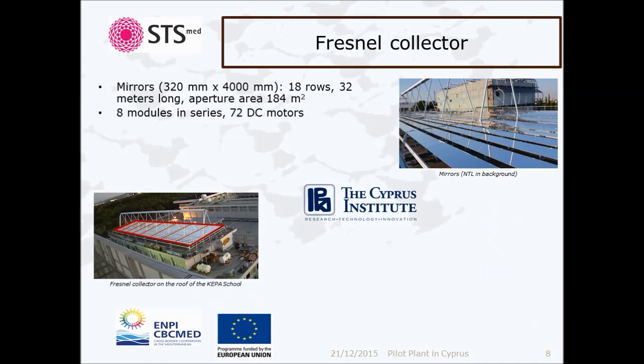The reflective field is composed of 288 mirrors. Each mirror is 2 meters long and 32 centimeters wide. 16 mirrors are aligned per row, and the rotation is ensured by 4 DC motors. The field has an aperture area of 184 square meters. The pilot plant at the Cyprus Institute relies on 8 modules in series. 72 DC motors drive all the mirrors, 4 per each row.